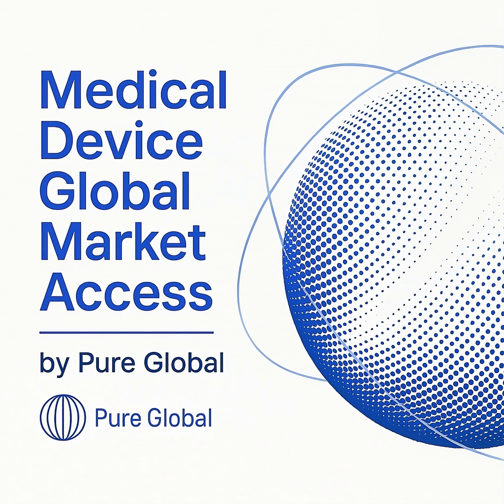This involves conformity assessment by an EU-notified body. After these deadlines, the UKCA mark will become mandatory for most devices. To get the UKCA mark, you must compile technical documentation compliant with the UK Medical Device Regulations 2002, and for devices other than the lowest risk class, undergo a conformity assessment with a UK-approved body.